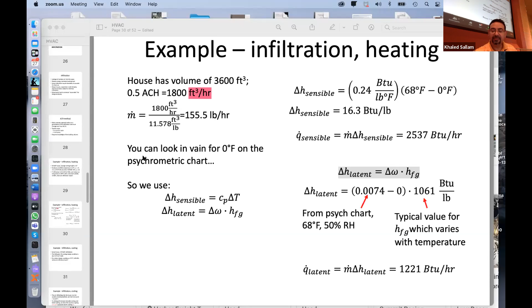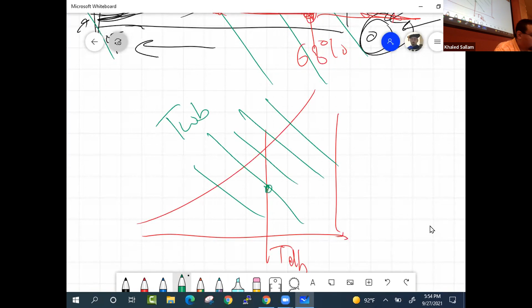Okay, cooling - the air is actually hot outside, 99 degrees with a wet bulb temperature of 75. He can give you the outside condition by temperature and phi, or on this chart he can give you the dry bulb temperature and the wet bulb instead. How do I get the wet bulb? Those lines, right, this would be T wet bulb. He said it's like 75 here, and this was 99, so you meet here.